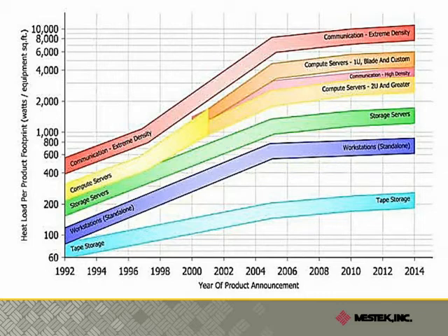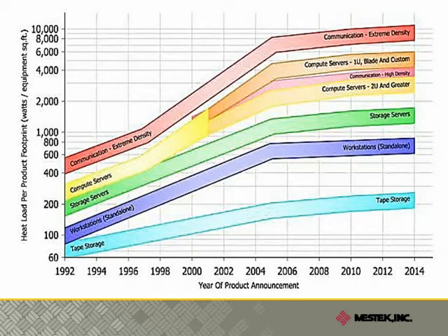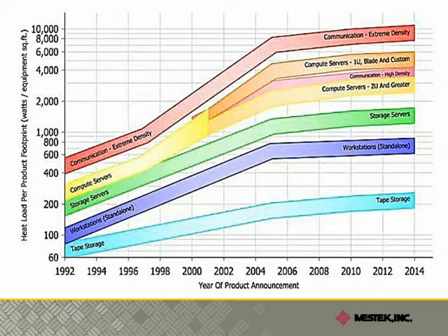That heat load is growing with the increasing server densities necessary to meet the rapidly growing demand for digital information transfer. While a typical commercial office building might have cooling requirements of 10 or 20 watts per square foot, some IT applications have cooling requirements approaching 10,000 watts per square foot of equipment. Even if you spread the equipment out over a warehouse-size space, it is obvious that the cooling load is enormous.